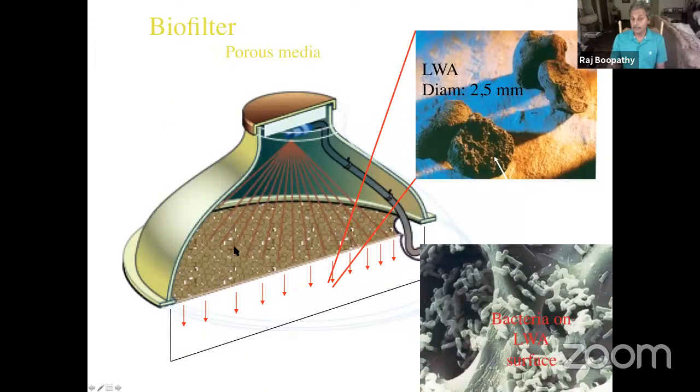And then we have biofilter. There is a lot of filter material we can use, like ceramics, rocks, plastic material. And then inside this biofilter, we have again biofilm. You can see bacteria attached to this biofilm. And then the concept is again the same. You try to retain this biomass. These are the good bacteria. They already remove the carbon. So you don't want to lose these bacteria along with the effluent. So you're keeping these bacteria in this biofilter, trapping them inside the reactor as long as possible.